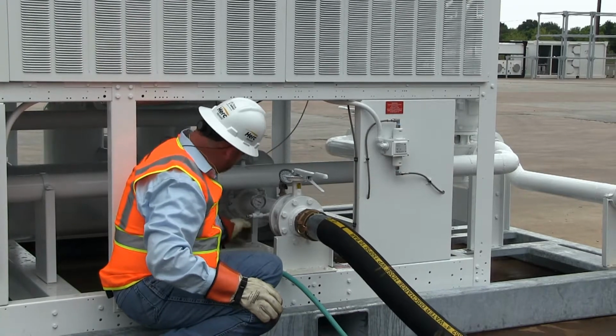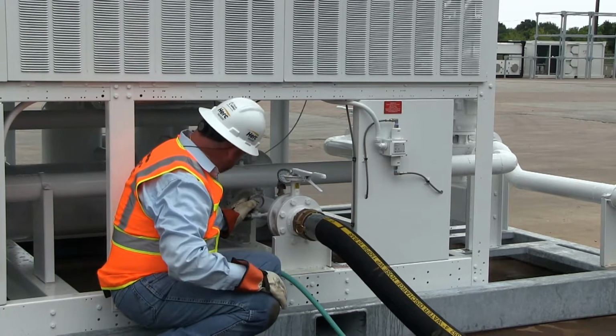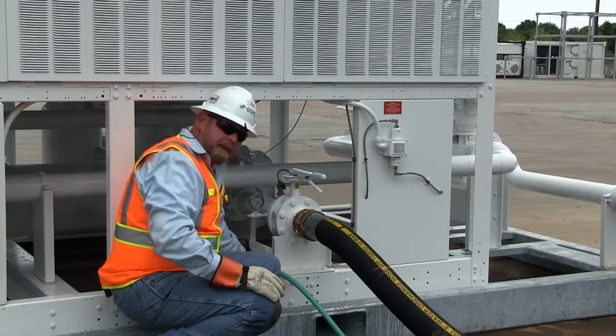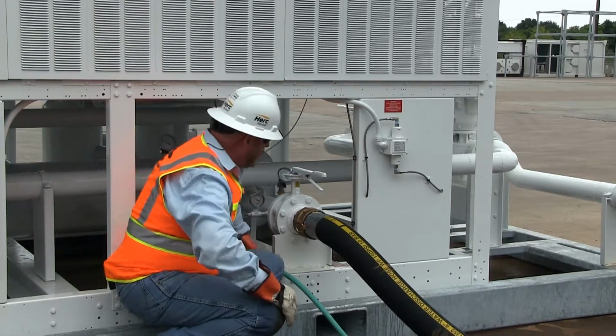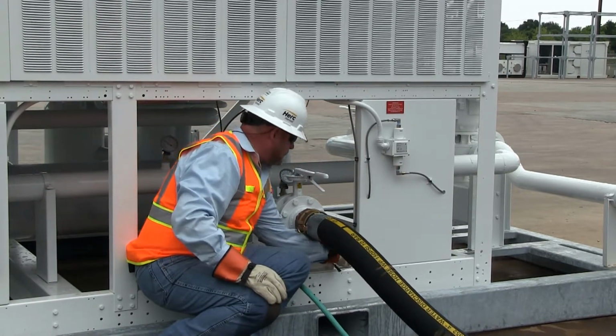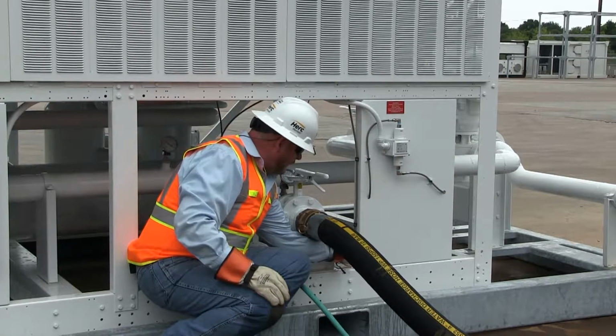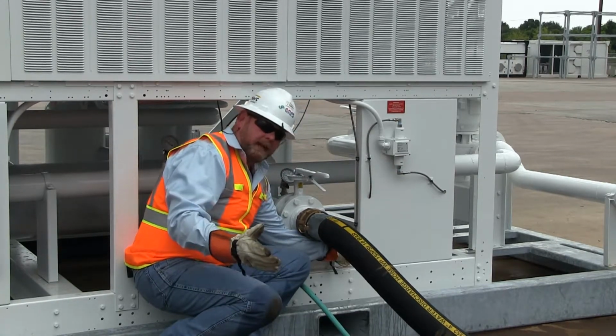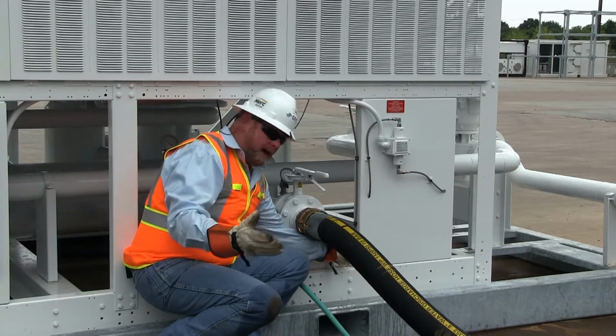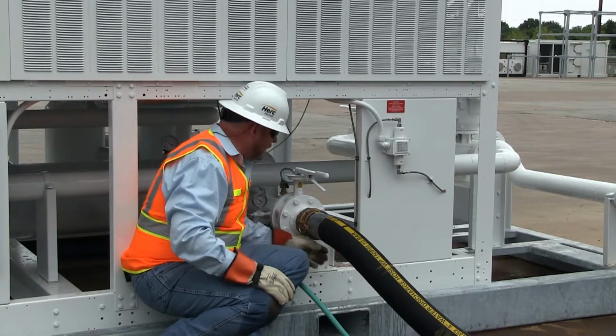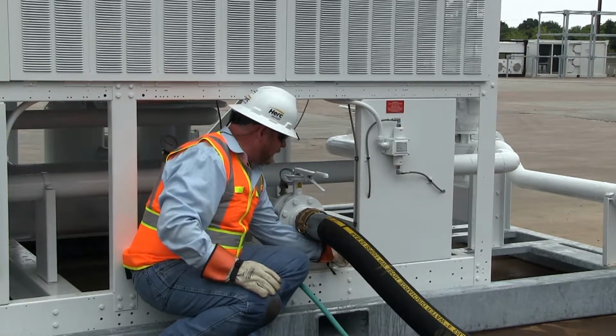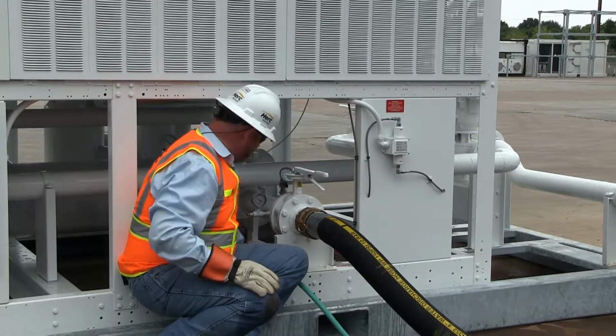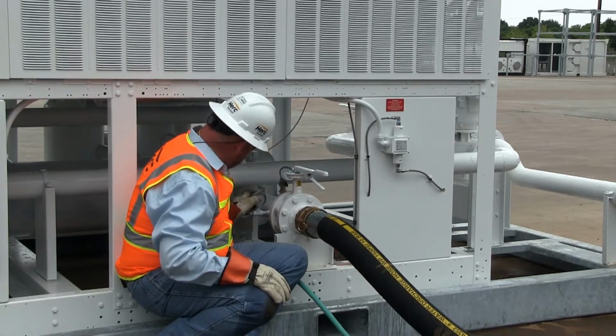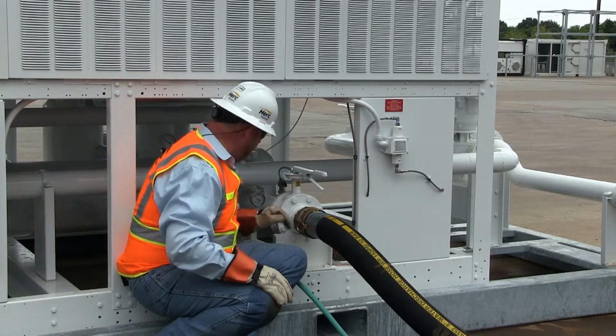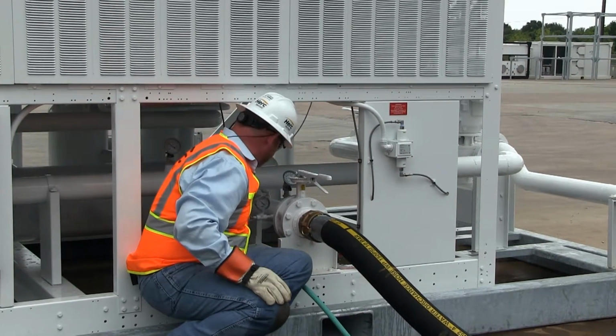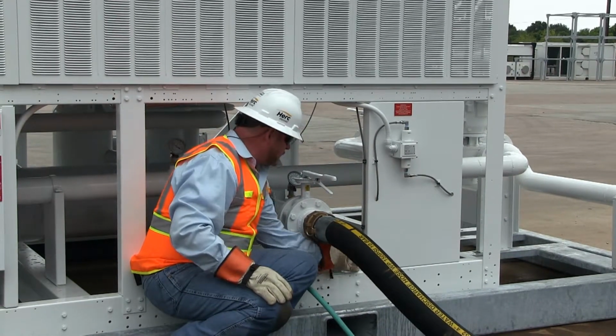So we filled our system up. We've done some preliminary bleeding of air, and we're at about 50 psi. So that's a good starting point. Our high point bleed is right here on this valve. We're going to open that up. You're going to hear the air coming out. Again, as we take the air out, we're going to open up the water and let it fill in. What we want to do is get 100% water coming out of the system while we're filling it, and I'm watching my pressure here. So now we've got all the air out. Looks like I got the system there for now. Close that off, and we'll close this off.